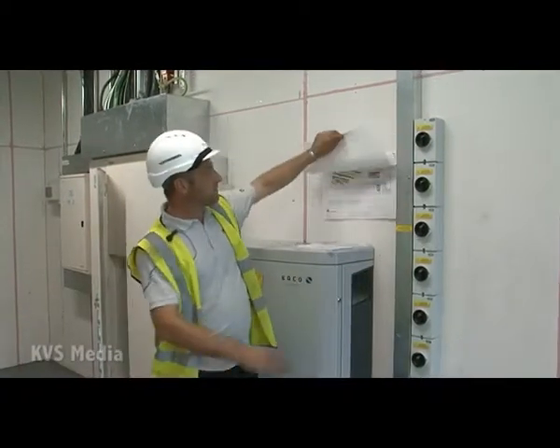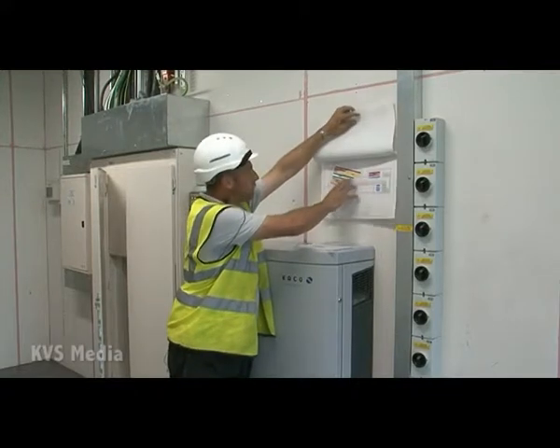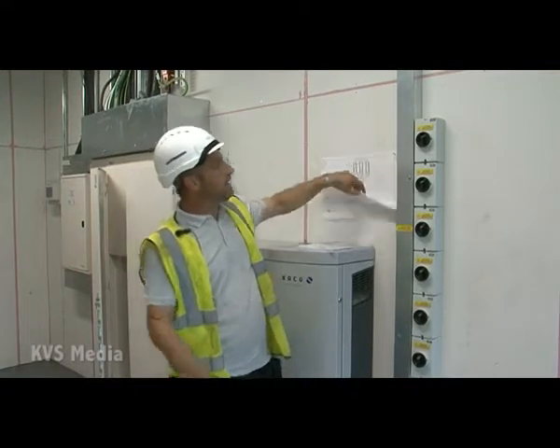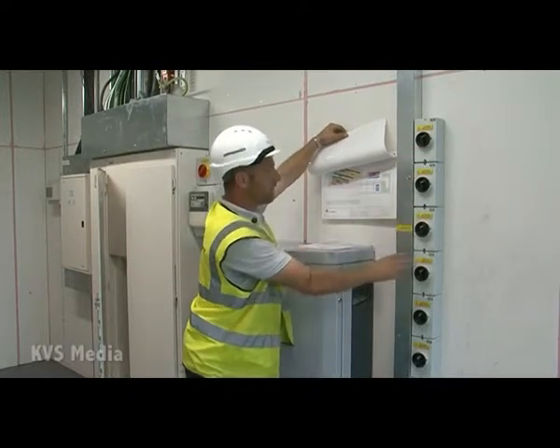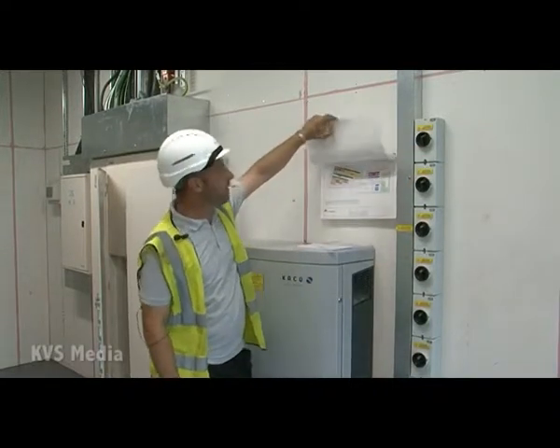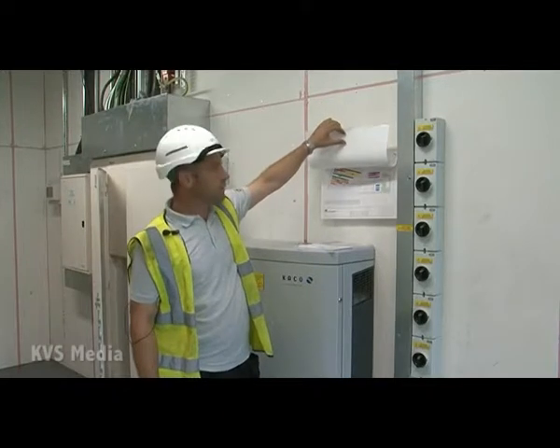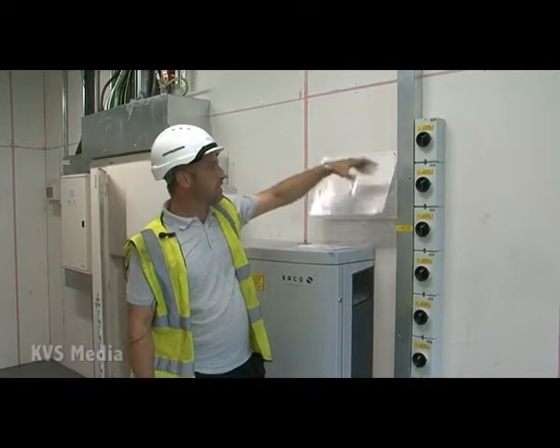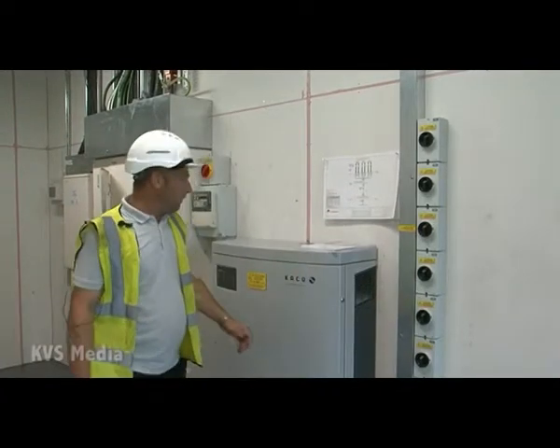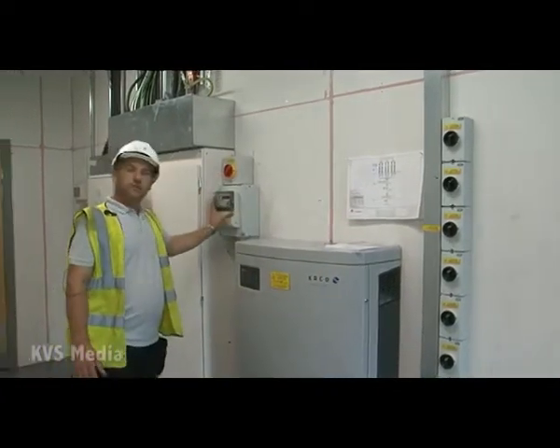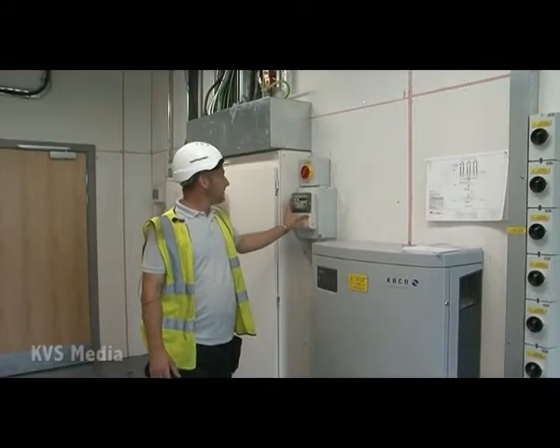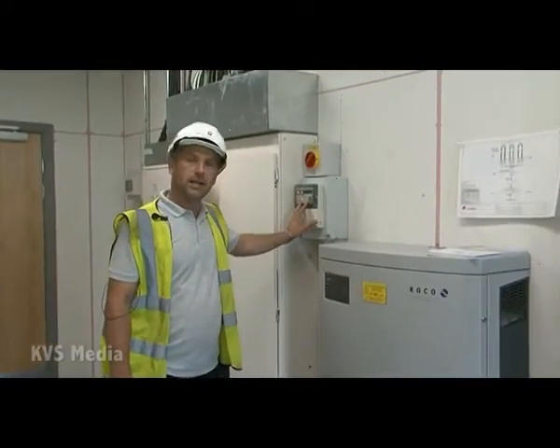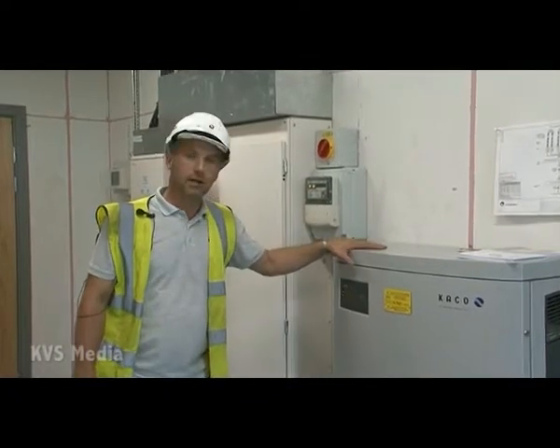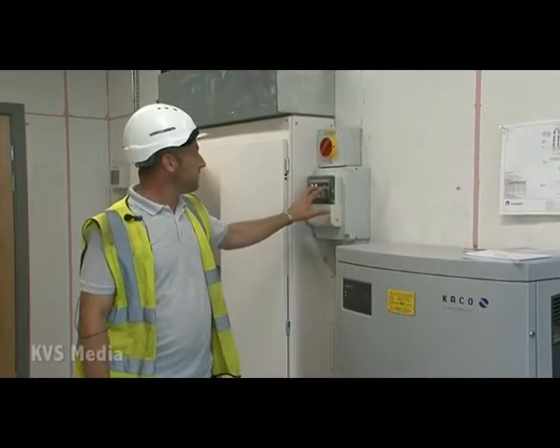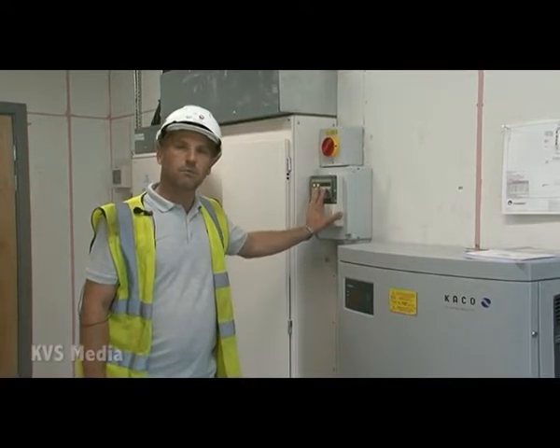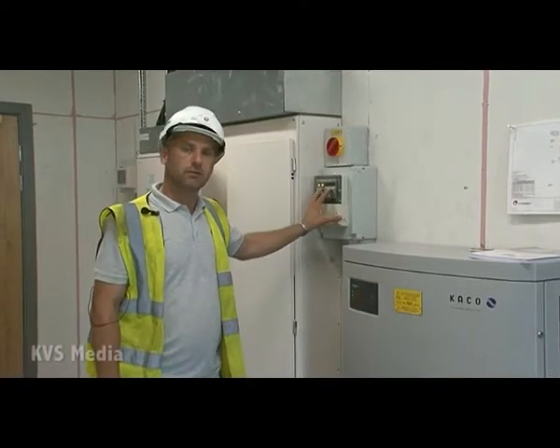There's one for each string. There is a string drawing just here which shows where all the strings on the roof are, and each one of these DC isolators will be labelled, and they show each isolated string. So if any strings need isolating, this is where it would happen. And then this is your generation meter. This measures all of the energy that has been created by the solar power, and this is where you will get your FIT reading from, which is needed every 3 months for your energy provider.